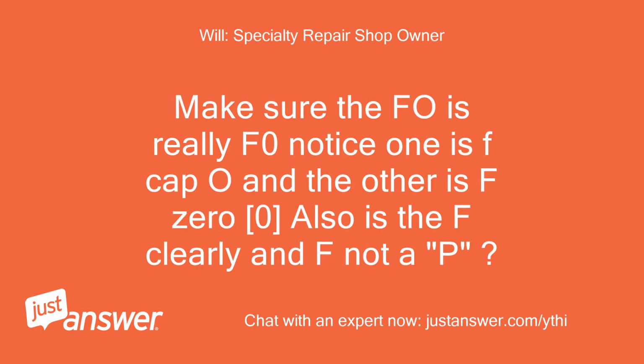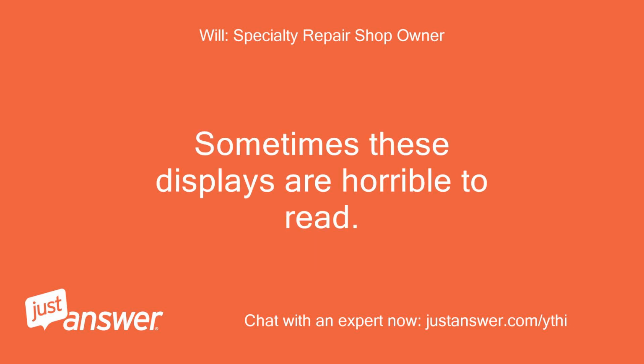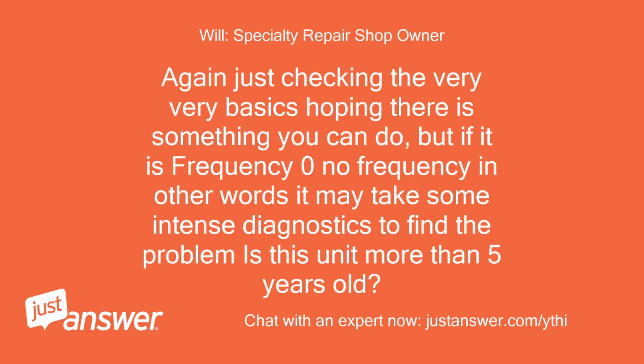Make sure the F0 is really F0. Notice one is F capital O and the other is F zero. Also, is the F clearly an F and not a P? Sometimes these displays are horrible to read. Again, just checking the very basics, hoping there is something you can do, but if it is frequency 0, no frequency, in other words, it may take some intense diagnostics to find the problem.